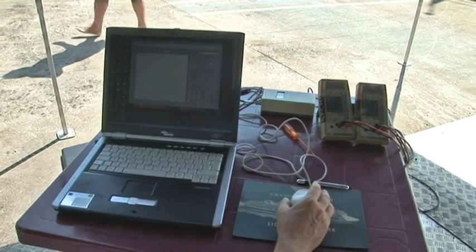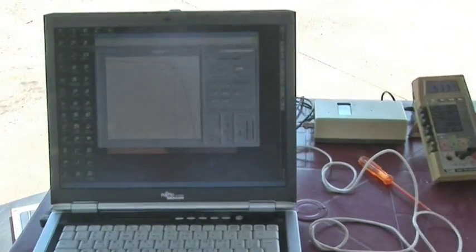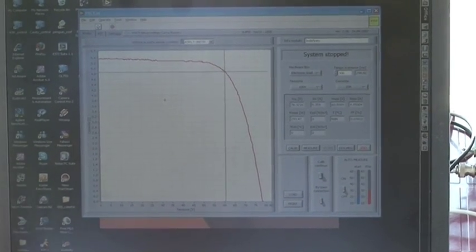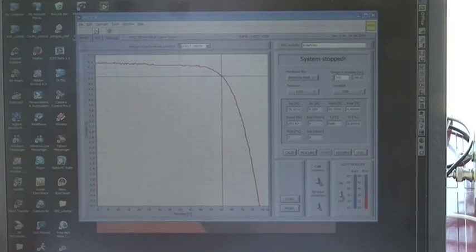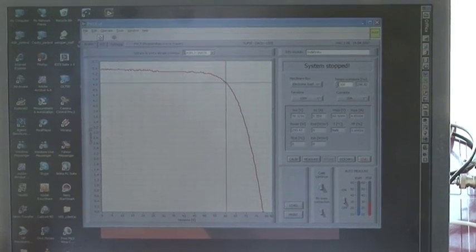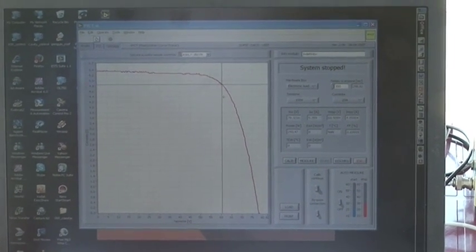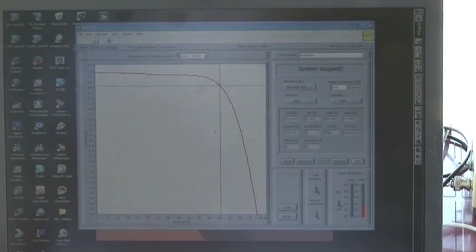This is the PC measuring the IV curve, which can be seen on the screen. What you see here is the IV curve, which gives a picture of the characteristics of the panel — from the so-called short circuit current here at this point, right through to the open circuit voltage down at this point here. This is the point of maximum power, which in this case is 293 watts. This is a nice smooth curve which shows that in this case the panels are working as they should be.